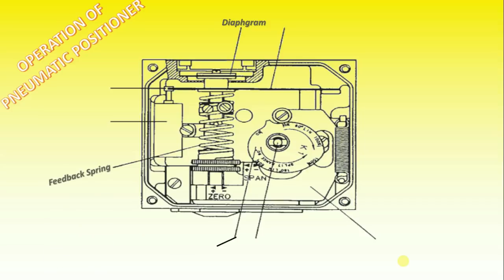The balance arm moves the spool in the pilot valve, furnishing supply air to the actuator, while at the same time air is exhausted from the actuator and vented to atmosphere through the pilot valve.